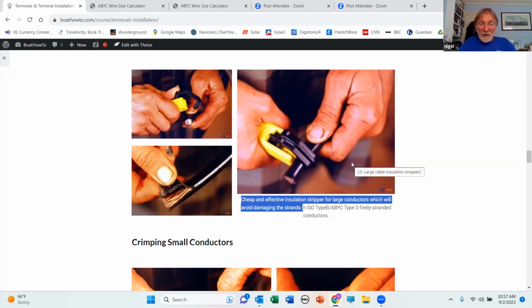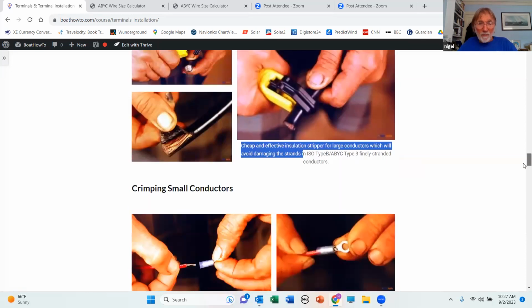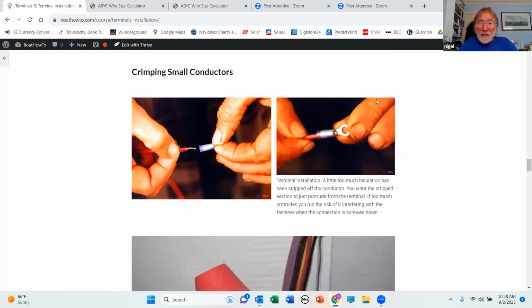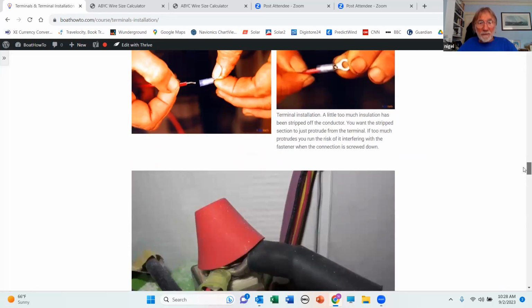We need to strip off enough insulation so that the bare conductor just goes through the terminal and pokes out the other end a tiny little bit, but not enough to where it's going to interfere with the contact area on the terminal. So we're going to push it in, and we've got a tiny little bit sticking out here. And then ideally, for most of our terminals, we want to buy ones with an insulating sleeve on them. Some of these sleeves are heat shrink, which we'll get to in a moment. You can shrink it down afterwards, but most of them are just plastic. And then you add heat shrink after the fact.